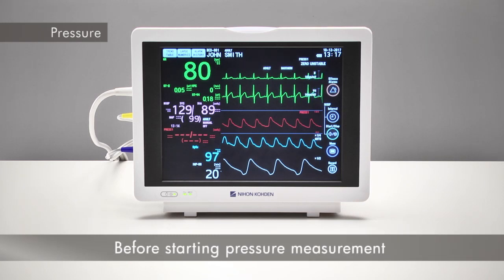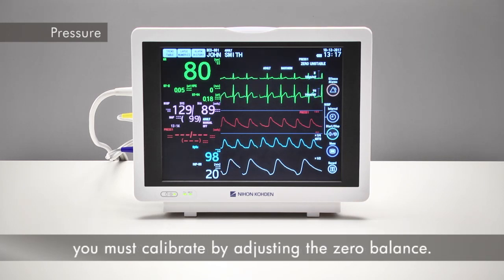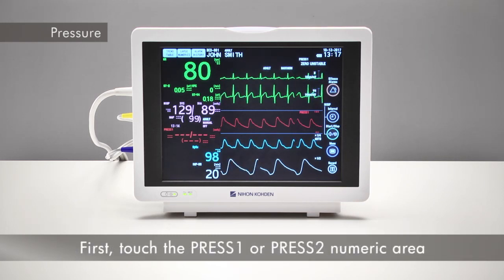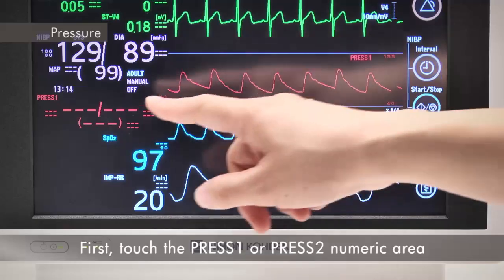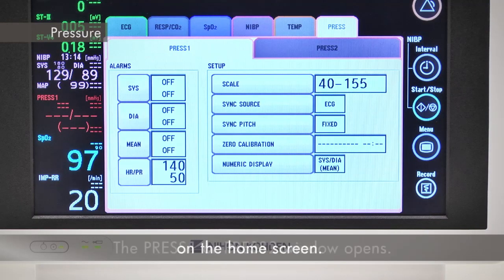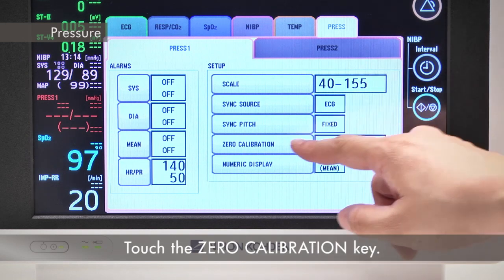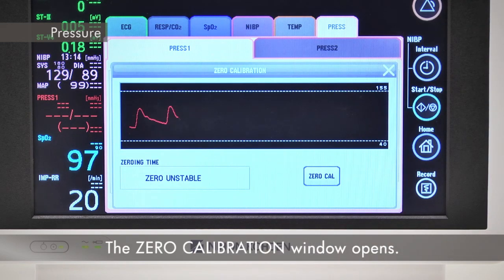Before starting pressure measurement, you must calibrate by adjusting the zero balance. First, touch the Press 1 or Press 2 numeric area on the home screen. The Press 1 or Press 2 window opens. Touch the Zero Calibration key. The Zero Calibration window opens.